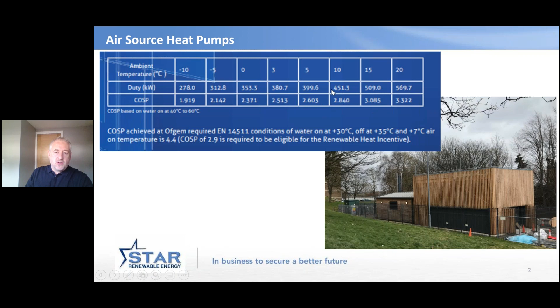But what we're doing here is we're raising heat up to 60 degrees with these coefficients here. So you can see just in the small text, heating based on 40 to 60 with that inlet air temperature. And so you can see the COP, the efficiency ratio, varies from less than 2 to over 3. And that's using a HFC working fluid, cousins of CFC, and now being phased down. But when we conceived this project a few years ago, that was the gas that was felt to be best to use. And they all give you a slightly different efficiency effect. But what we're getting is an efficiency, typically over the season, of about 2.7 or so.